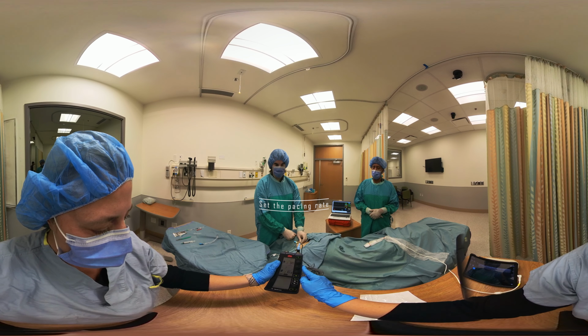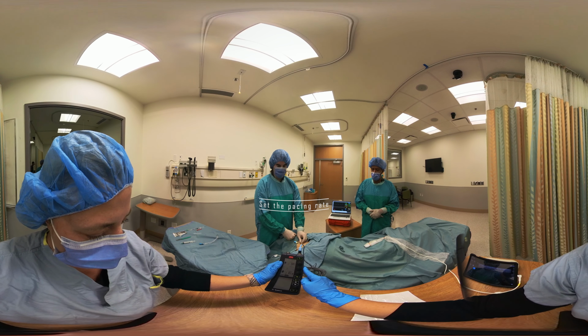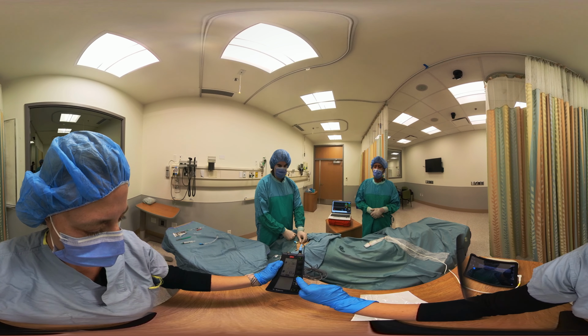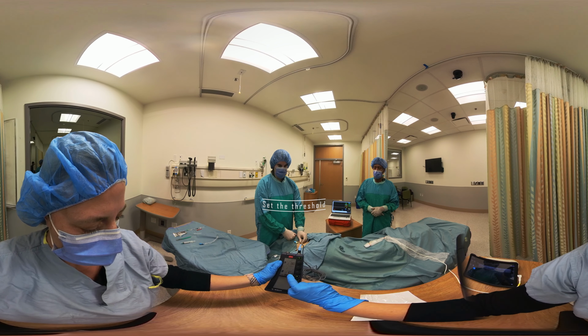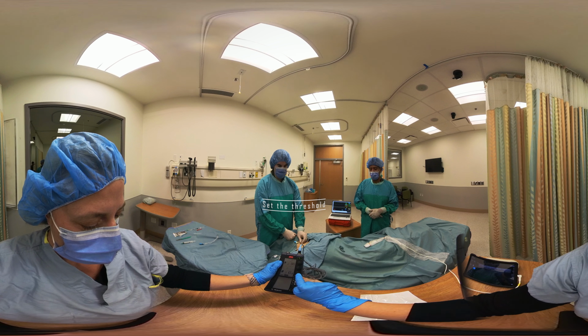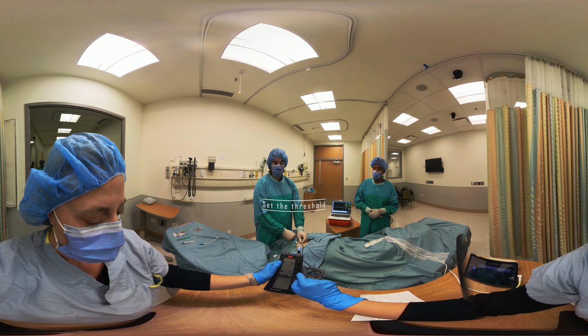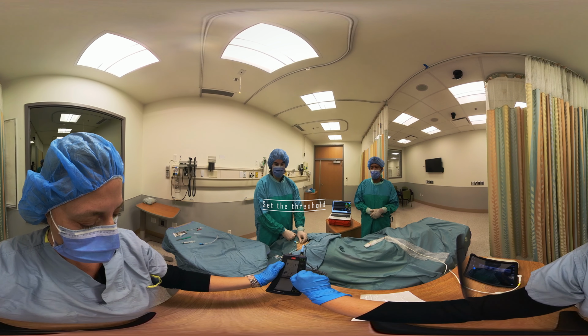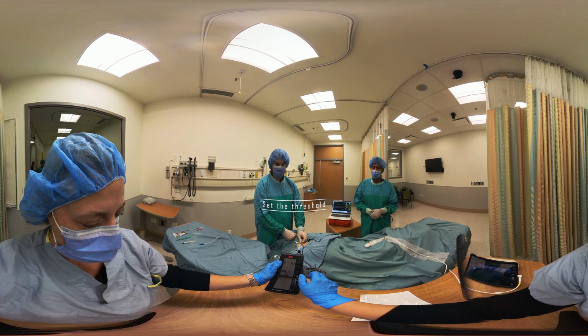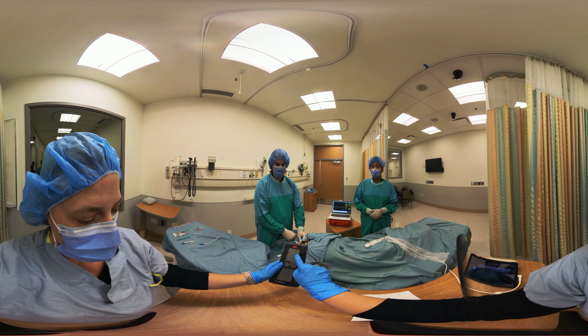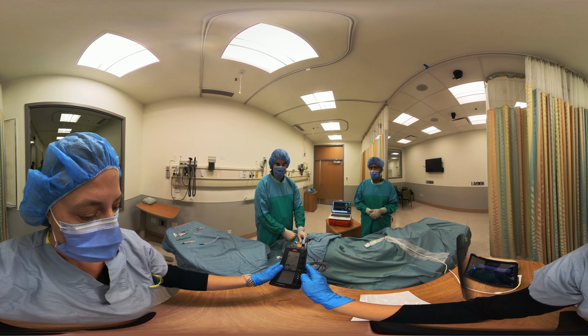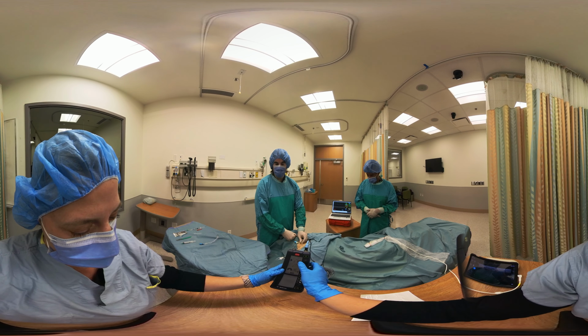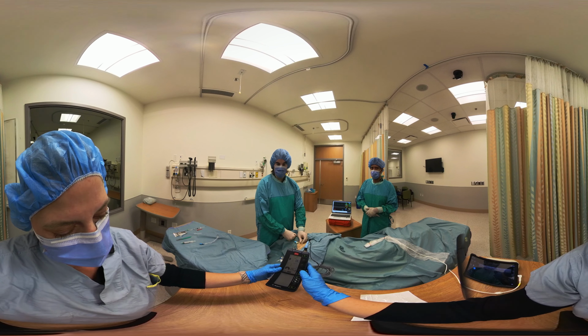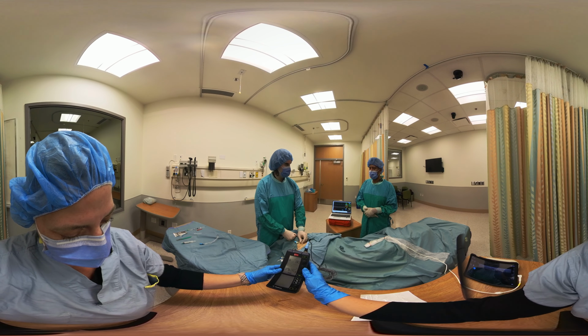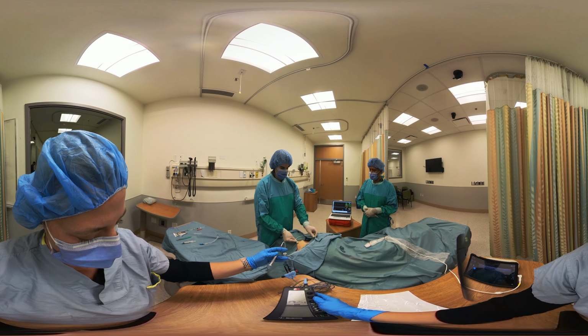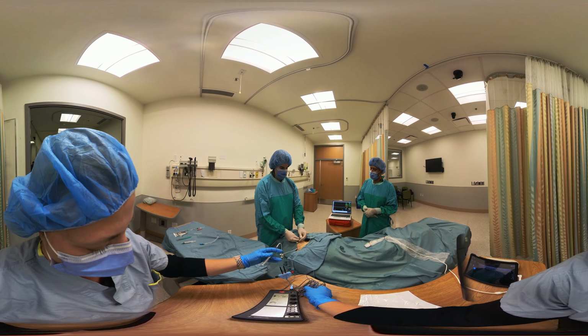So we increase that rate after pressing the unlock button on the pacer. Also, we will need to increase the threshold. The threshold is the amount of electrical output that the pacer gives. We want to have a very high output, so we'll go up to 25 millivolts so that when we go in, we are ready to capture. You would like to verbalize the settings that you're on at this time to your primary operator. Rate of 80, output of 25 on VOO. Perfect. And so now the primary operator will insert the catheter.